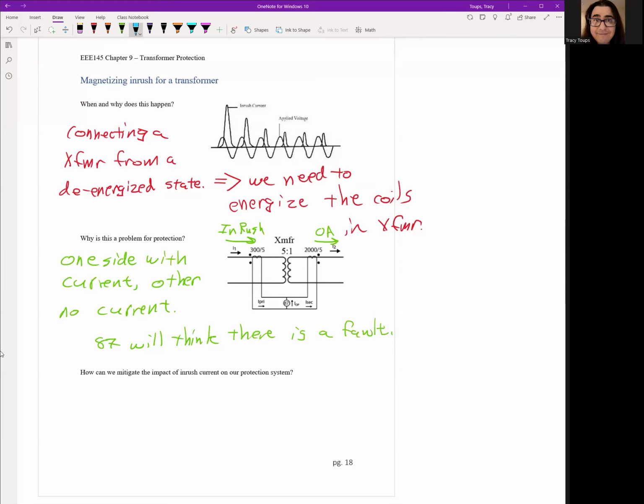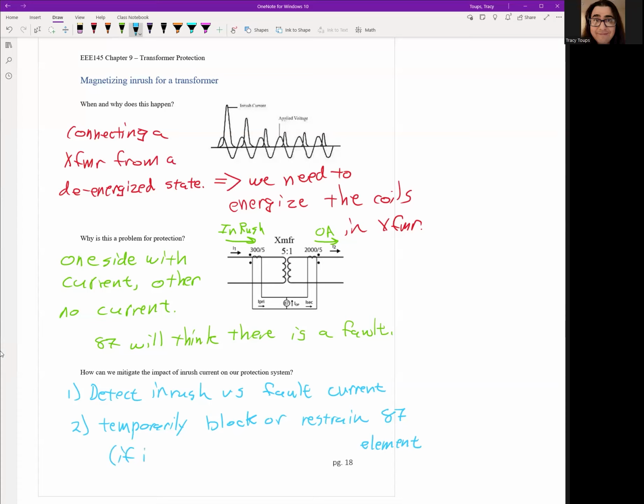Okay. So the question is, how can we mitigate the impact of inrush current on our protection system? One, we need to detect inrush versus fault current, right? We need to differentiate the difference between these two. Number two, we need to then temporarily block or restrain the 87 element. Okay. So as long as we can detect it as inrush, then we can block or restrain the 87 element. And then we'll say if inrush current. Okay. You definitely don't want to do this during a fault, because then you're defeating your whole system. Okay. So that's kind of the roadmap we're going to try to do.